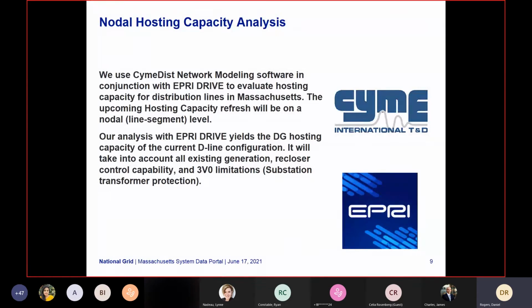So like I mentioned before, our future hosting capacity analysis is going to be nodal. So this will show a segmented analysis and data for every segment. So it'll have the high and low hosting capacity range for that segment, as well as the mainline voltage. So with certain lines that we have step down transformers. Just because a distribution line coming out of the station starts at 13.8, that doesn't mean the whole main line is slated to be that voltage. A lot of the times halfway down, we'll drop it to 4 kV for certain reasons, and that will decrease the hosting capacity because it now is dependent on the ratings for those step down transformers.